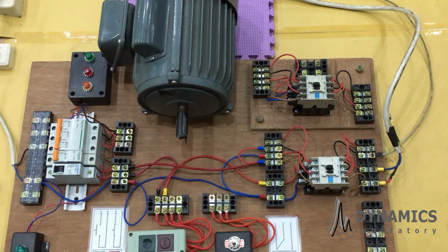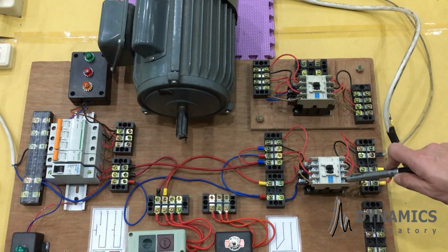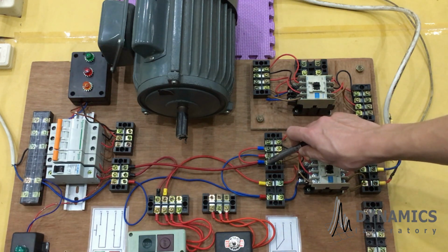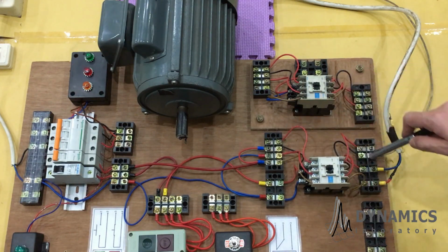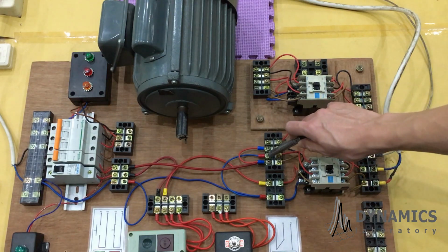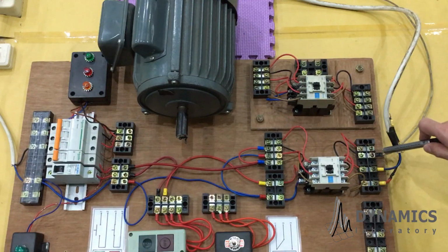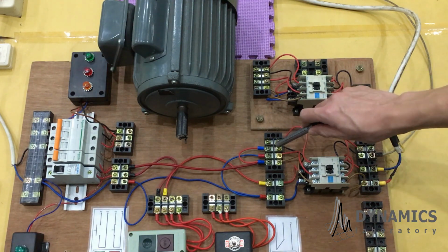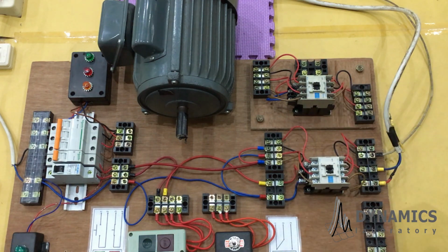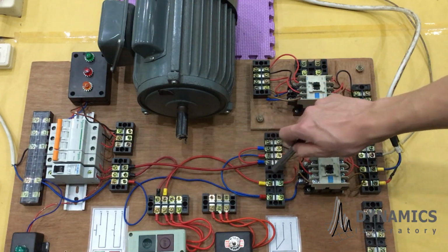From the previous explanation, I have already explained to you that main winding should be connected to live and neutral terminal. That's why red cable from main winding will get live terminal. Blue cable from main winding will get neutral terminal. And for auxiliary winding, it's up to you if you want to connect it with live terminal or neutral terminal. But for this example, I connect auxiliary winding with live terminal. This is our load circuit.